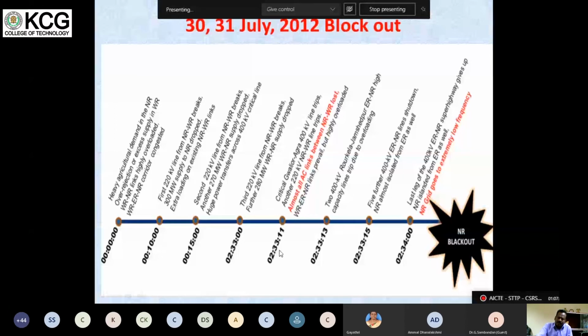So what happens? The 400 kV Rourkela-Jamshedpur line also, from the eastern region to the northern region, a high capacity line, trips due to overload. So again, a further 400 kV eastern region to northern region line also shuts down. So what happened at 2 hours 34 minutes? The total NR grid goes to extremely low frequency, leading to a northern region blackout. So unless the voltage and frequency in the grid system are maintained, it is very difficult to maintain grid discipline or avoid grid failure. So grid failure can be avoided by maintaining voltage and frequency in good condition.